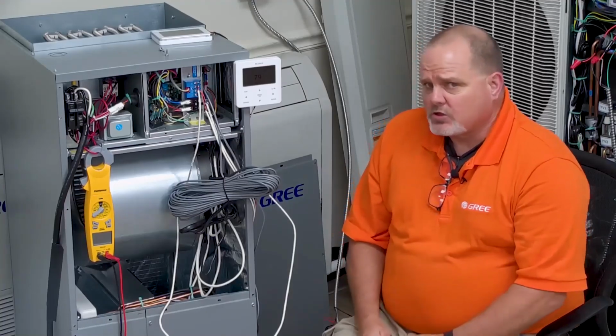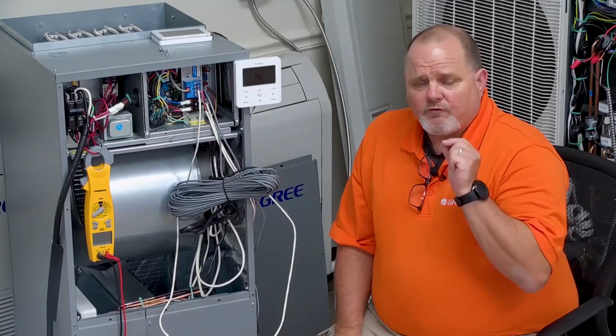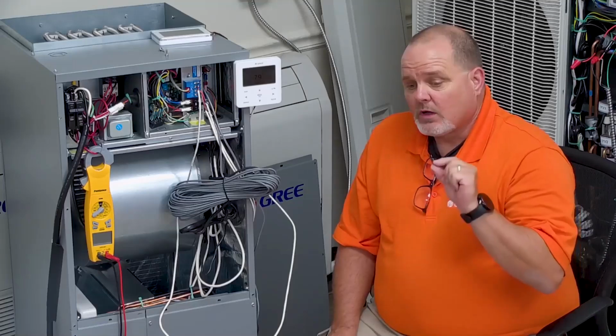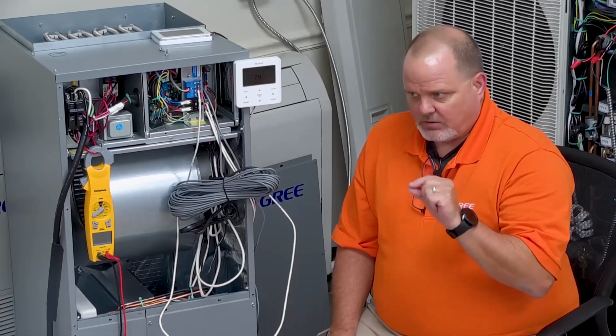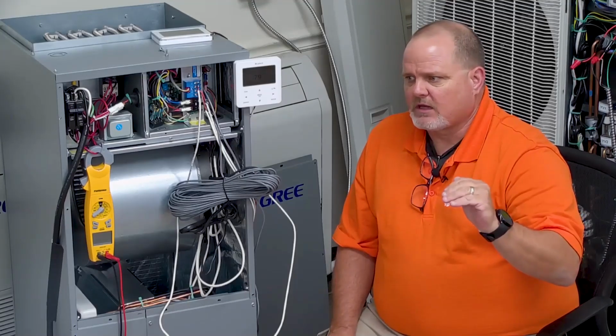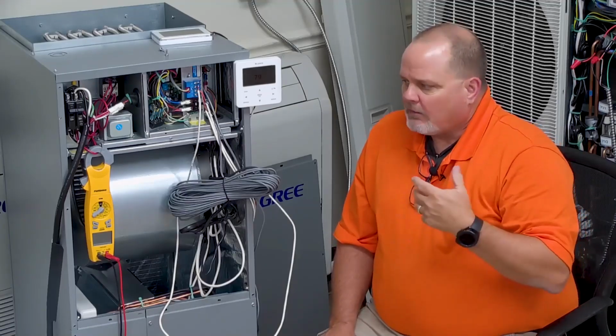With this controller, we have the ability to set it up in two different ways. You can set it up to where it will finish the heat call with the auxiliary heat. Once the auxiliary heat calls for, it will finish the call. In other words, it will not shut off the electric heat until the thermostat is completely satisfied. Or you can set it up to where it does not satisfy the thermostat completely. So basically the first stage or the second stage gets satisfied, electric heat drops off, and the heat pump stays on. Let's say the temperature drops a little bit again, then the auxiliary heat comes back on, that part gets satisfied, and it goes back to running the heat pump. It can just keep cycling like that, keeping the heat pump running the entire time, somewhat maintaining the temperature with a little help. Like I said, you have the option to set it up either way. You can make it just satisfy the thermostat and shut the whole system down, or you can set it up to where auxiliary heat only cycles in when it needs to.